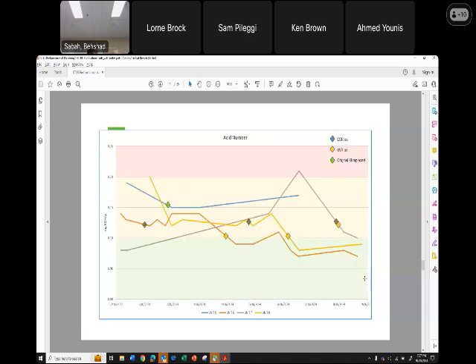Next. So acid number, same thing. We're trying to bring the acid below 0.10. And on three units towards the very right of the graph, you could see that we've basically achieved that. On unit five, our control unit, we're still using the old IX resin from before, and we're barely able to maintain 0.15.